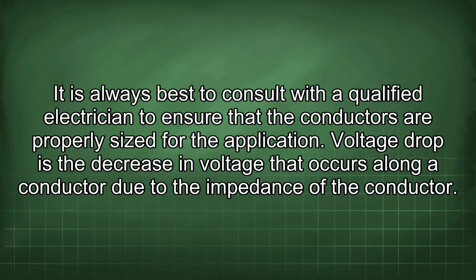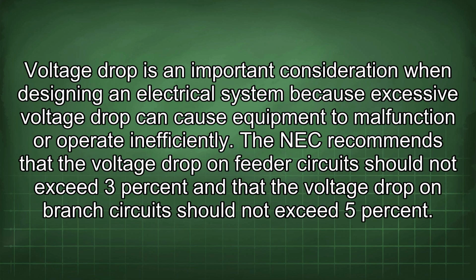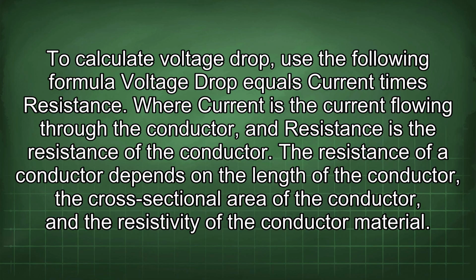application. Voltage drop is the decrease in voltage that occurs along a conductor due to the impedance of the conductor. Voltage drop is an important consideration when designing an electrical system because excessive voltage drop can cause equipment to malfunction or operate inefficiently. The NEC recommends that the voltage drop on a feeder circuit should not exceed 3% and that the voltage drop on a branch circuit should not exceed 5%. To calculate voltage drop, use the following formula: voltage drop equals current times resistance, where current is the current flowing through the conductor, and resistance is the resistance of the conductor.